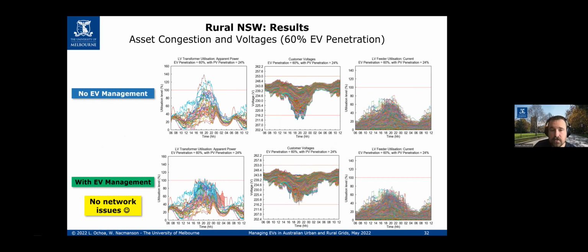This is just an example—feel free to look at the report for more detail. Without management we have issues: voltage problems, asset congestion, the transformer going over the limit. With EV management, we bring that below the technical limits and manage the voltage issues without any forecasting, largely solving those problems. Any slight overloads could arguably be within cyclic ratings, since these are nameplate ratings rather than cyclic ratings, so those slight overshoots could still be within design specifications.